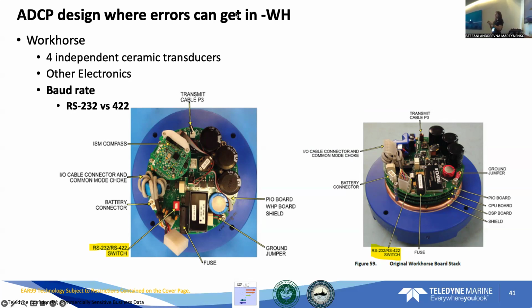It can sometimes, in transport or even just on the ship, get jostled and get stuck in between the 422 and the 232. That can lead to some comms errors. So that's my first pass check. If there are any issues, it's cable resistance, loop back, which I'll talk about in a bit, and then checking and making sure that switch is in the right position.